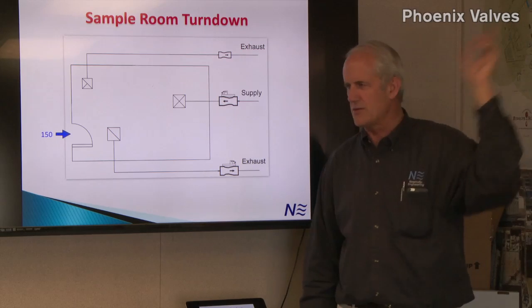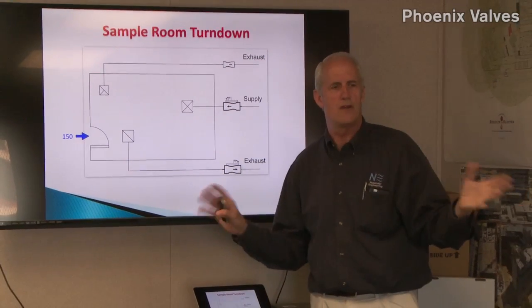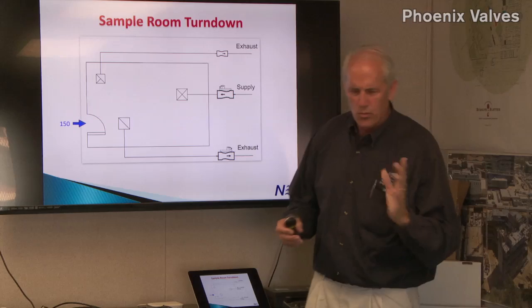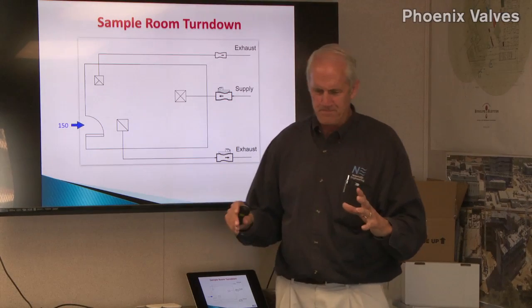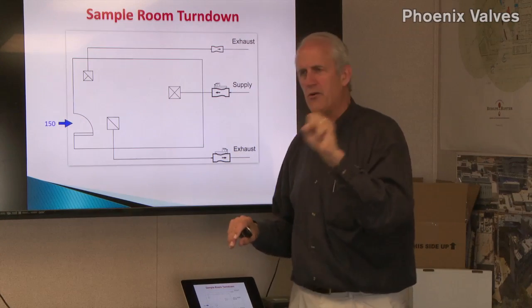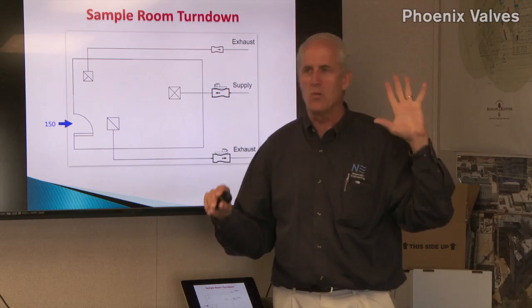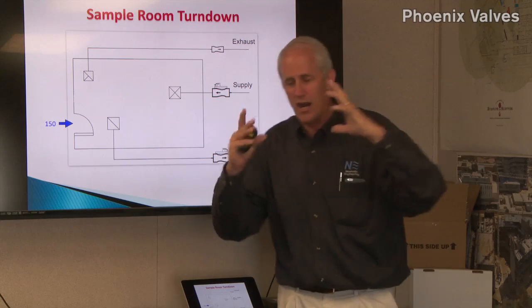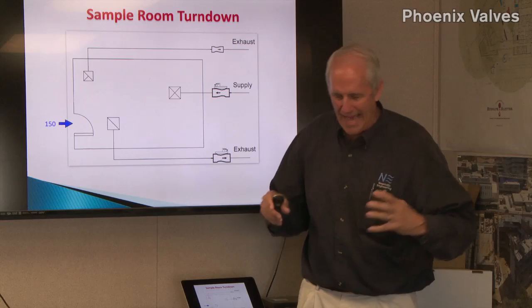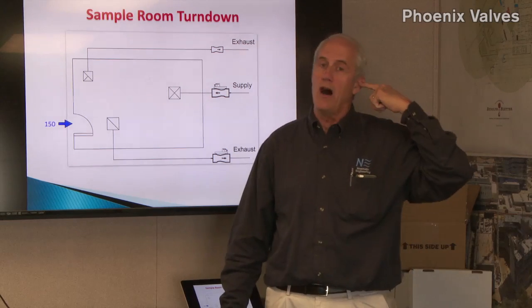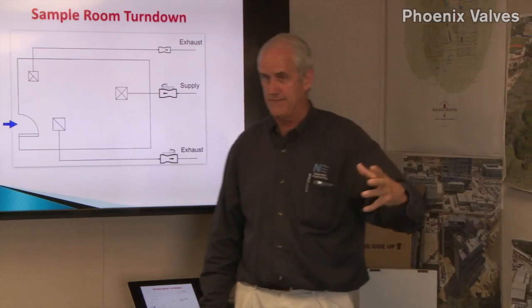I think the best thing might be just to go out there, look at a few of the rooms, look at a few of the valves. We've got fume hood monitors out there. If the fume hood monitor alarms, you're going to want to know that. And just so you know, our fume hood monitor has two different audible and visual alarms. So by listening or looking at the alarm, you can tell what the source of the problem is. That's kind of important to know.